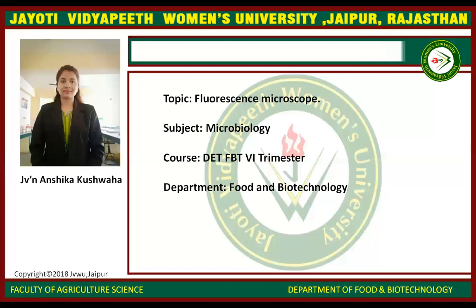The typical components of a fluorescence microscope are a light source and the excitation filter, the dichroic mirror, and the emission filter. The most common fluorescent microscopes in use are epifluorescence microscopes, where excitation of the fluorophore and detection of the fluorophore are done through the same light path. These microscopes are widely used in biology and are the basis for more advanced microscope designs.